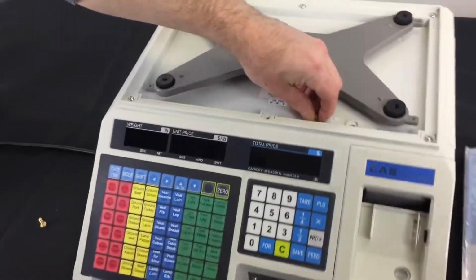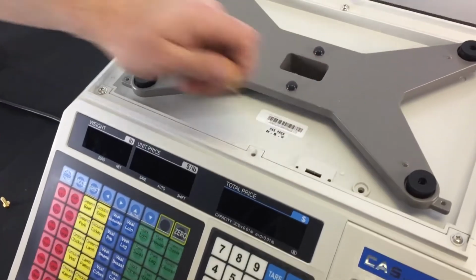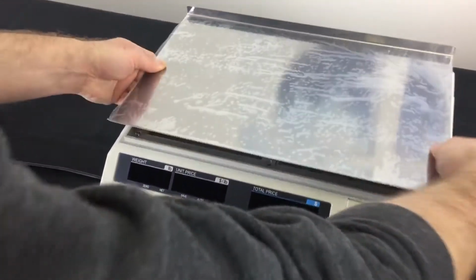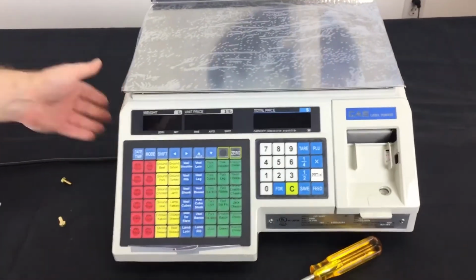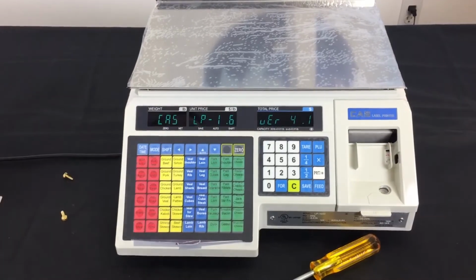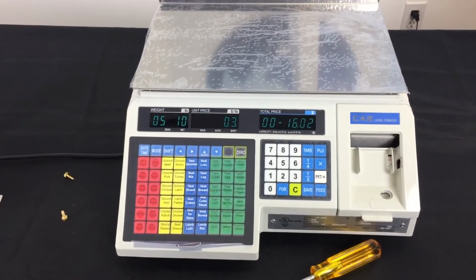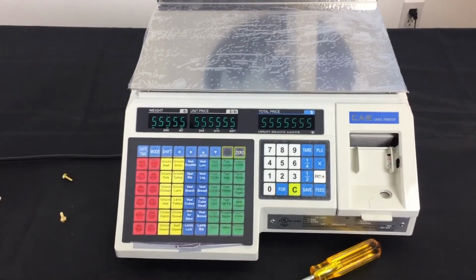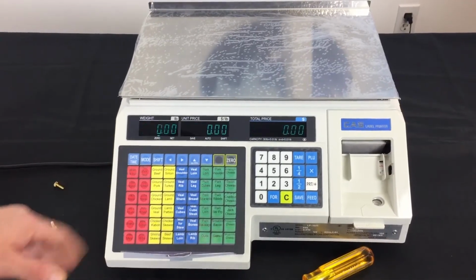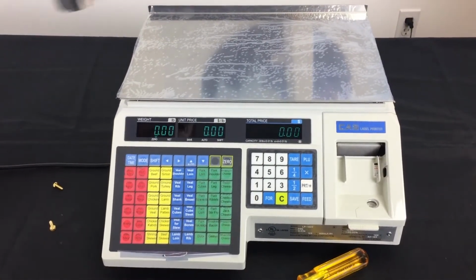Now you're going to want to slide that switch back to the right side in order to put it back into regular weigh mode. And we're going to place the platter back on the scale in order to test our weight. So we're going to power it up, wait for it to count up, go into the weigh mode. Going through our count now. Once we get into the regular weigh mode, we want to test our weight.